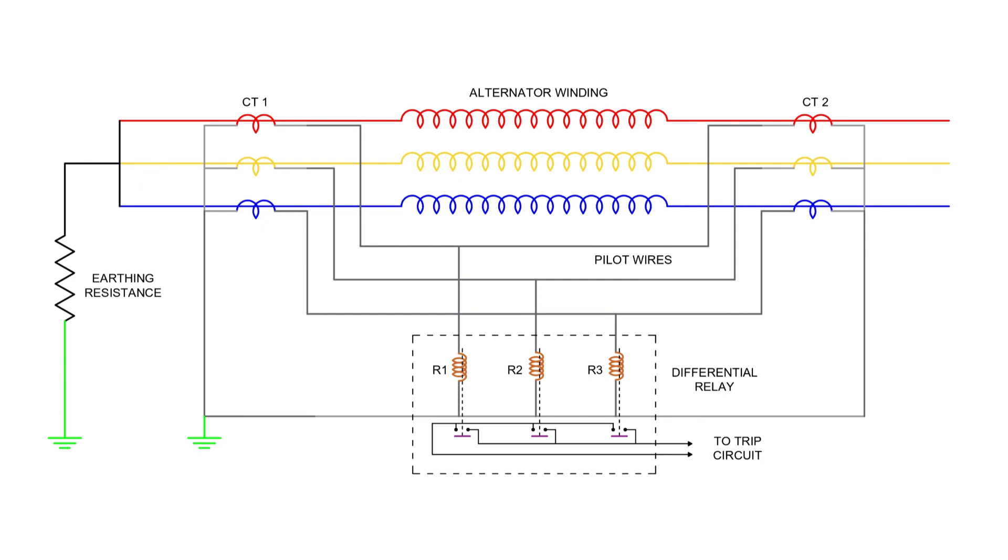Now, have a look at the schematic shown on the screen. It represents a three-phase alternator protected by differential protection. On each phase, R, Y, and B, we place two identical current transformers, one on the neutral side and one on the terminal side. These CTs monitor the current entering and leaving the stator windings.